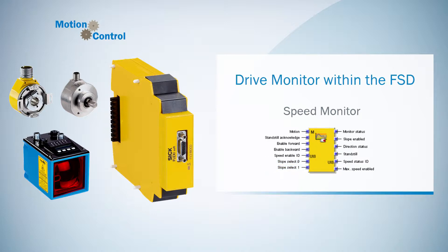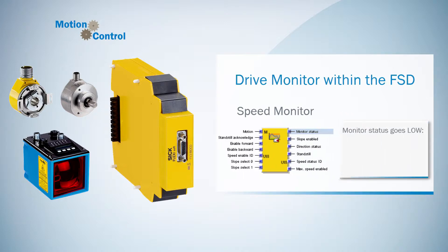Now the outputs. The output MonitorStatus is normally high. It goes low if one of the following monitoring functions has the result zero: monitoring of the reduced speed selected via the input SpeedEnable ID, monitoring of the maximum speed, and direction monitoring.